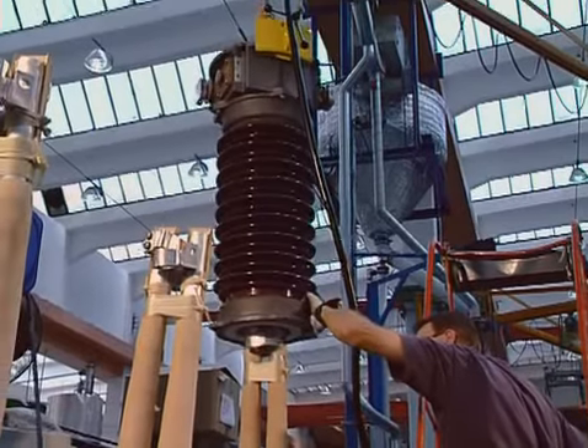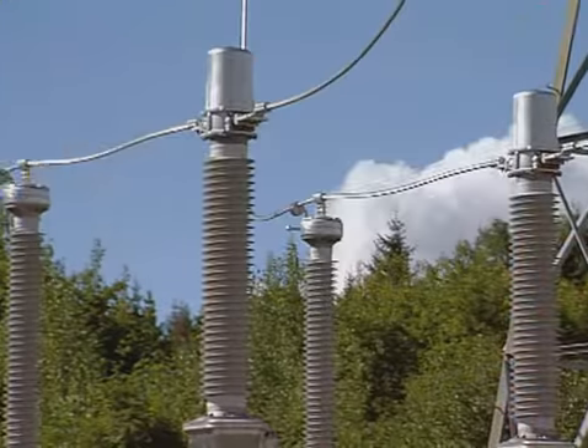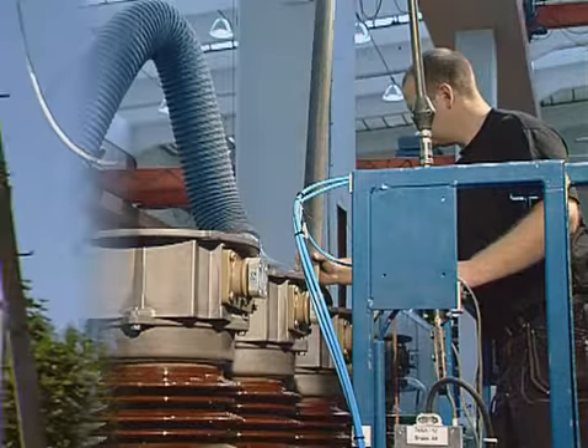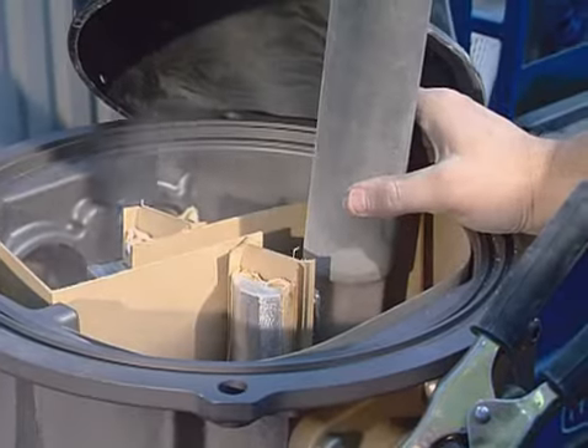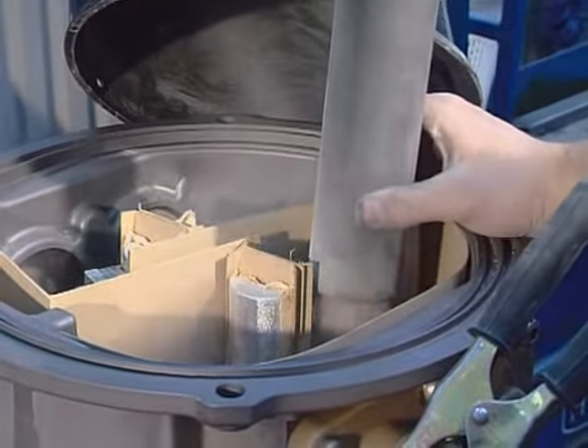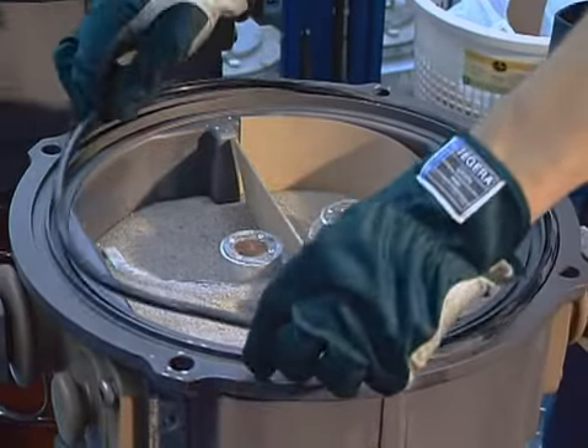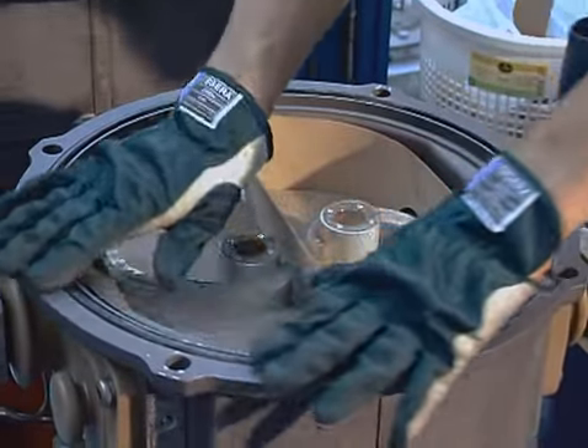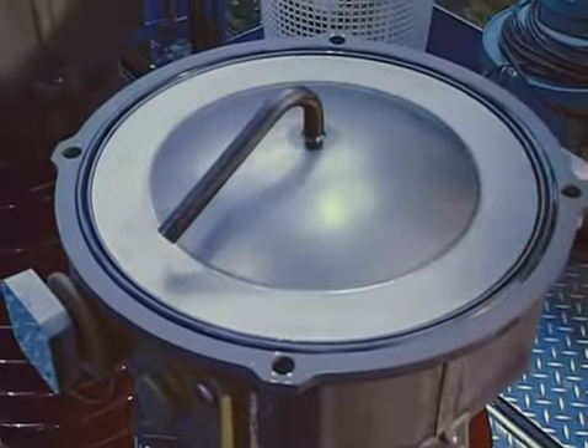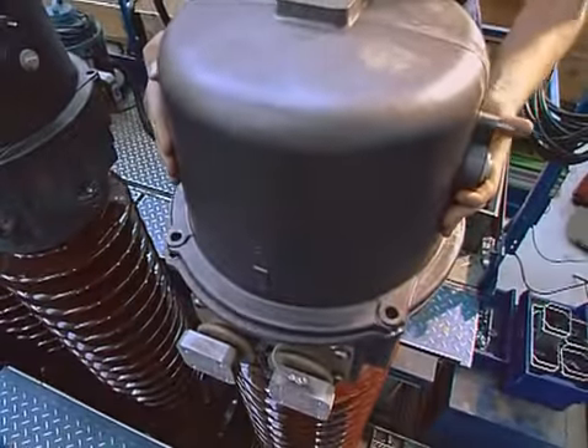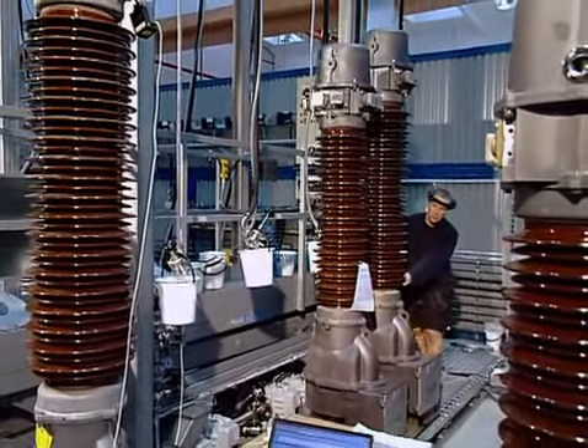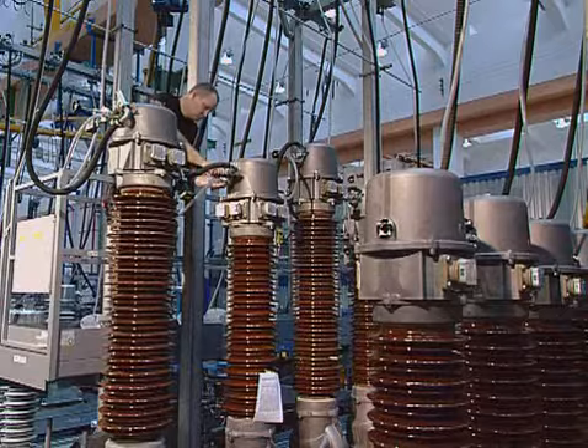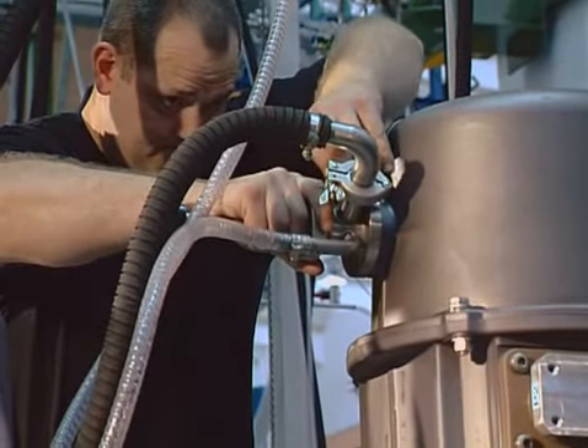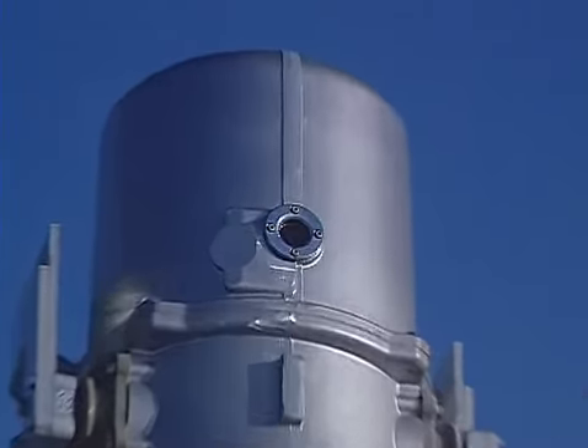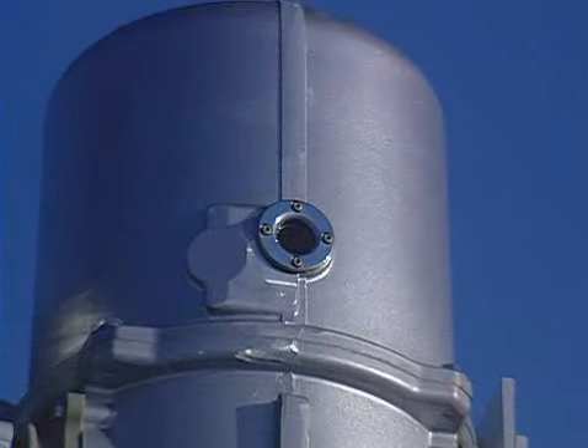Insulators are available in either brown or gray porcelain or in the ever more popular composite insulator. The current transformer is filled with pure silica sand in order to reduce the amount of oil and in order to stabilize the mechanical property. This unique method has been used by ABB for more than 50 years. The expansion vessel is mounted at the top. The assembled current transformer is filled with oil while exposed to heat and vacuum. Thanks to the design of the oil sight glass, the oil level can be easily checked.